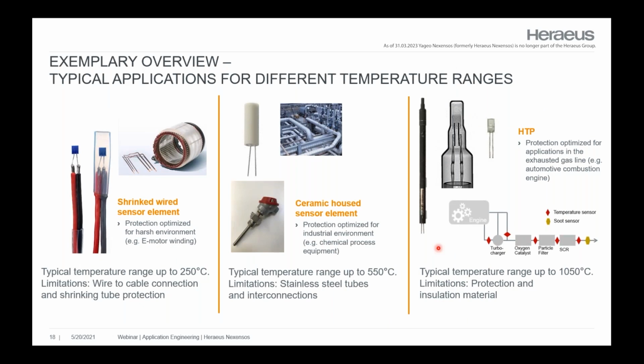Here are some different examples where you see how these temperature steps could be overjumped. On the left side you see that application in the E-motor. You have the shrinked wired sensor element, which has really good performance in terms of sealing, vibration, and resistance in mechanical topics. But on the other hand, there is a temperature limit, which is limited to 250 degrees.